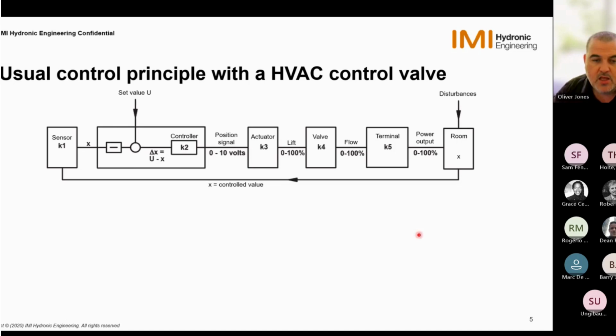When the actuator is at the correct position, the valve will be at a different lift, which will also be a different kV from when it was further open or further closed. And depending on the available kV value and the available differential pressure at the valve at that point in time, a certain flow rate will be flowing through the valve. And according to the flow that is now flowing through the terminal unit, we will get a thermal output coming out of the terminal unit, which will hopefully compensate for the deviation in the room and satisfy our room temperatures.